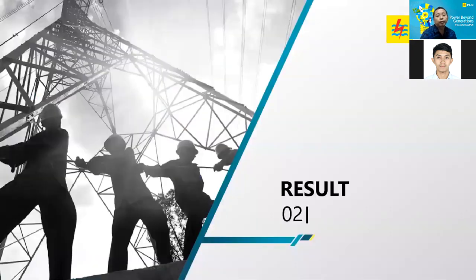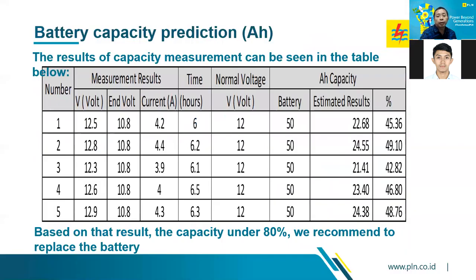Result: battery capacity prediction in ampere hours. The result of the capacity measurement can be seen in the table. As you can see in the table, all the predictions in 5 tests are between 42.82 and 49.1. Based on the result, the capacity is under 80%, so we recommend replacing the battery.